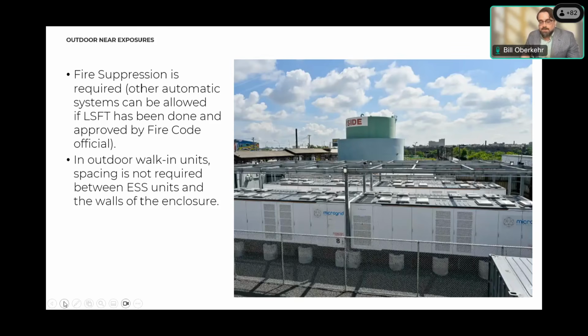The authority granted to the fire code official is specifically to confirm whether the siting decisions made in the project design are consistent with the data from the large scale fire testing. The code is not saying, based on the intent of the folks who wrote this, Paul included, that we can just disregard large scale fire testing results. The fire code official's authority is to say yes, these siting decisions are supported by the data from the large scale fire test, or no, they are not. So it's important to clear up where that authority lies, because that language appears over and over again in the code.